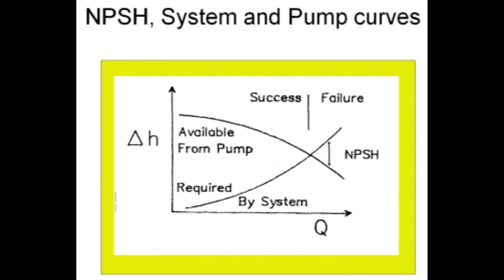And the implication there is that it's possible to cause problems for the pump by having a vacuum on the suction side, and that's what net positive suction head is all about. It's trying to ensure that we don't have cavitation or bubbles forming on the suction side of the pump due to a lack of pressure, due to either trying to pull up from too high a distance or even friction loss through the fittings on the suction side of the pump.